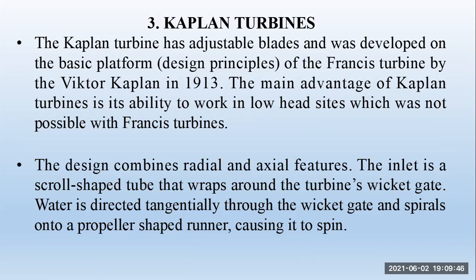The design combines radial and axial features. The inlet is a scroll-shaped tube that wraps around the turbine's wicket gate. Water is directed tangentially through the wicket gate and spirals onto a propeller-shaped runner, causing it to spin.